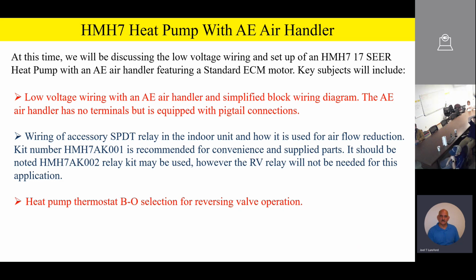And on the furnaces, they're an actual hard screw terminal. But on the block diagrams, just to make it easy to look at, I'll have just a block that says W1, and so on, and that'll be our connection. Just remember, they're pigtail connections on the AE air handler. We're also going to talk about the wiring of the accessory single pole double throw relay in the indoor unit and how it's used for airflow reduction.